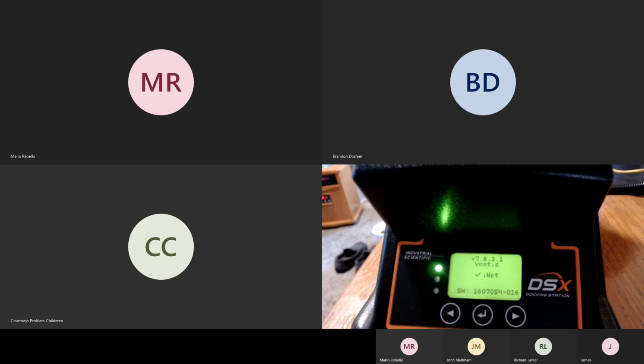Okay. So a lot of times, if you get a calibration failure where the LEL, H2S, and CO failed, but HCN and O2 passed, what that's going to tell you is that the bottle that has the CO, the H2S, and the LEL in it, your mixed bottle, something's not connected right. Because that's a gas delivery issue, whenever three of those sensors that all come from the same bottle don't pass. Now, again, if all those fail and the HCN fails, but O2 passes, I would check all your gas connections on the back and make sure they're actually connected properly, because then it's showing me that it probably was sucking the wrong gas whenever it should have been sucking the other gas.